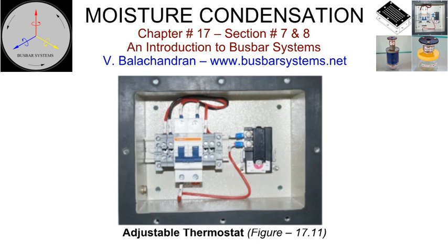Thermostats can be installed with either a fixed setting or with variable settings. Knowing the site conditions for a project, it is preferable to have a fixed setting for a thermostat. The use of an adjustable thermostat is an invitation for the user to reduce the thermostat setting to save energy, in the process, significantly increasing the likelihood of condensation.